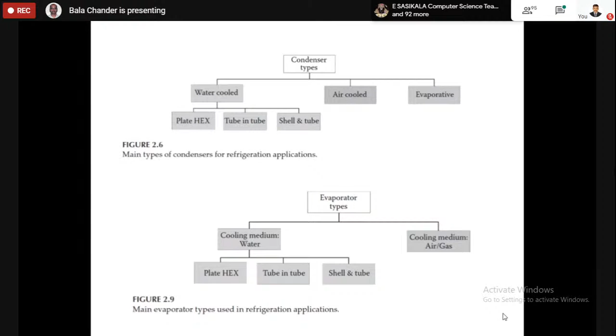There may be air cooled and water cooled condensers, and sometimes in larger capacity they go for evaporative cooled condensers. For the preferred type of condenser in larger capacity, they go for shell and tube heat exchangers and also plate heat exchangers, which are now used in many industry processes. Nowadays, if there is water scarcity, even for larger capacity systems, air-cooled condensers are preferred. Even in the 5 to 10 TR capacity we have air-cooled condensers, mainly due to maintainability. Generally, the fin and tube heat exchanger is used as the condenser type.